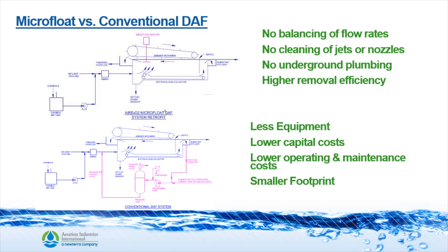Highlighted in pink are the equipment that is different for each of the systems. On the top, you can see you will use a microfloat unit to produce the micro-bubbles. On the bottom diagram, you will see that you need to have some piping, a recirculation pump, an air compressor, an air regulating valve, an air dissolving tank, and a valve controlling the flow back into the system.